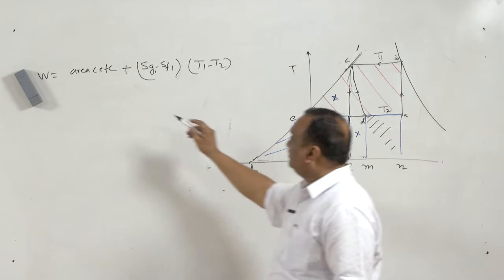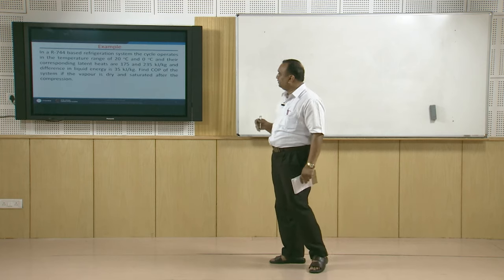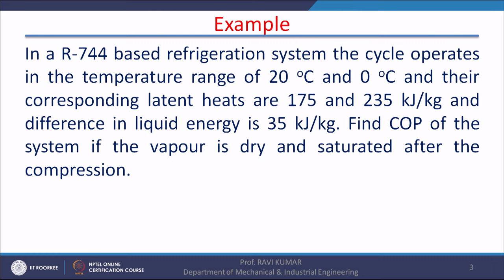In order to have a clearer understanding of this process, let us work out one example. An example is given: in an R-744 based refrigeration system — R-744 stands for carbon dioxide — the cycle operates in the temperature range of 20°C and 0°C, and their corresponding latent heats are 175 and 235 kilojoules per kg. The difference in liquid enthalpy at 20°C and liquid enthalpy at 0°C is 35 kilojoules per kg.